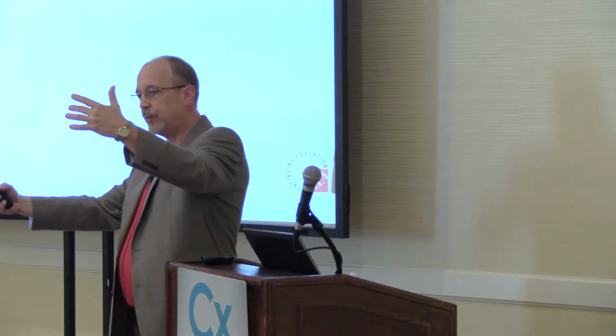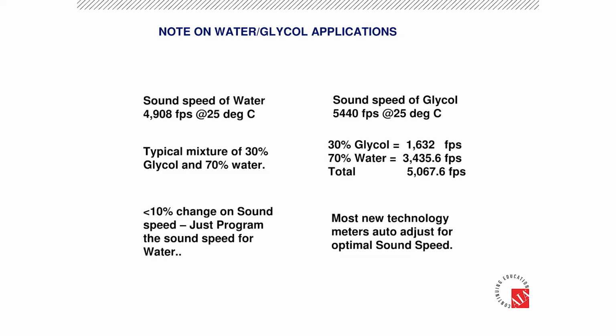And the other part is some of the newer flow meters actually compensate for this if you have different liquids. So with some of the newer ultrasonic technologies out there, if you were to have water and 30% glycol, in the days of yore, you'd have to factor out the sound speed of the water and the sound speed of glycol and calculate the ratio. So using that method, the speed of water was 4,900 feet per second, and the speed of glycol was 5,400 feet per second. I was going to use a 30% mixture of glycol and 70% of water, and basically this would equal 5,000 feet per second. And you'd have to go to 'other' and type in 5,000 feet per second to get it to work.